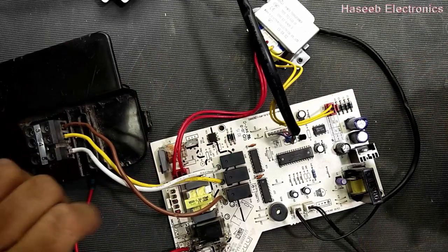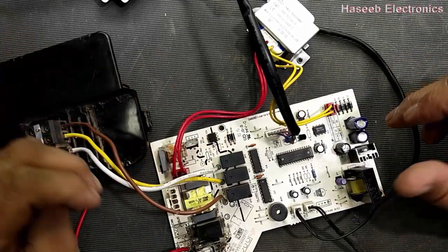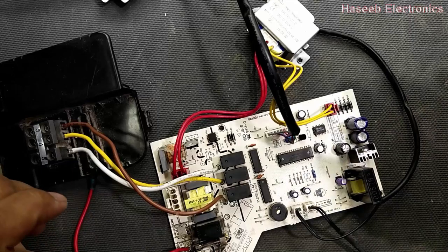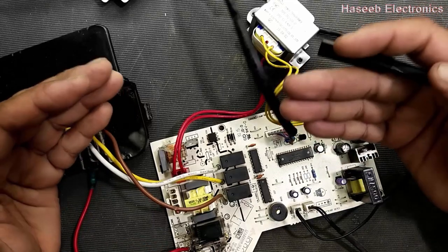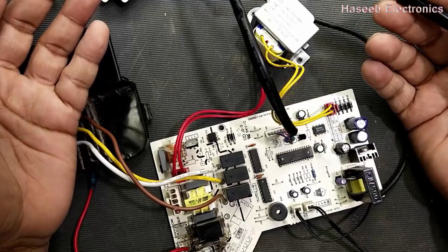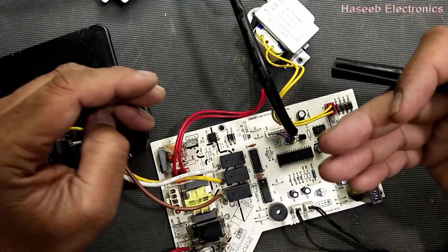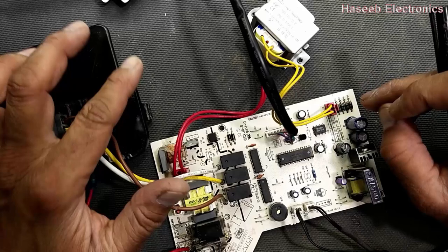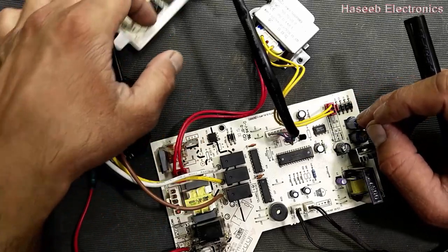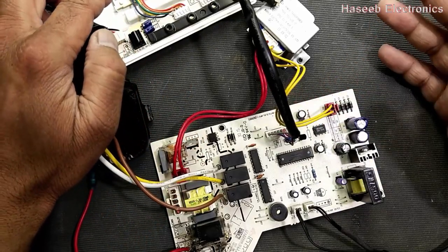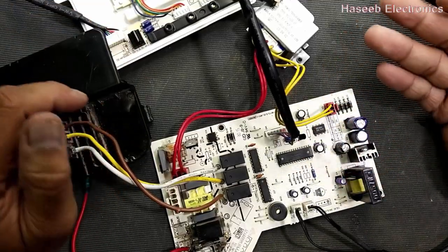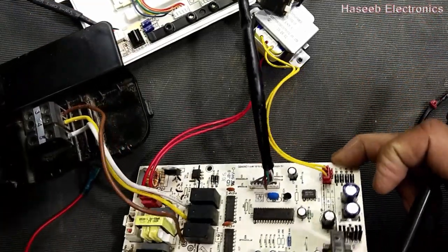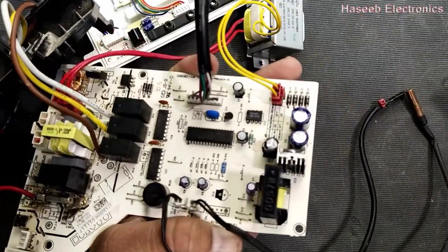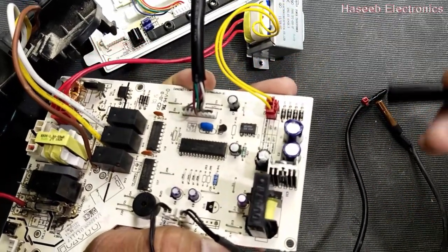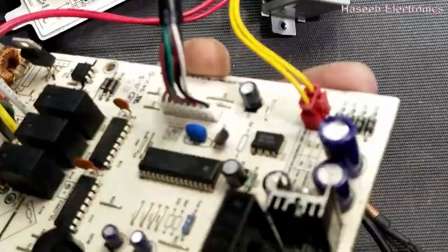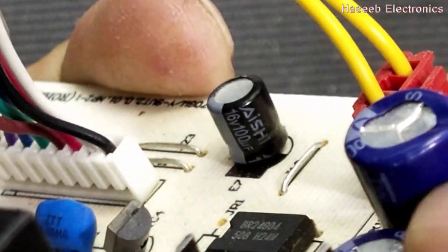This board has problems. The first problem: no power on. No power in the indoor unit and outdoor unit. At first it was not displaying anything, and sometimes it was working, sometimes not. After that it stopped working, and when the technician removed it from the indoor unit, we could see this capacitor's outer body damaged.